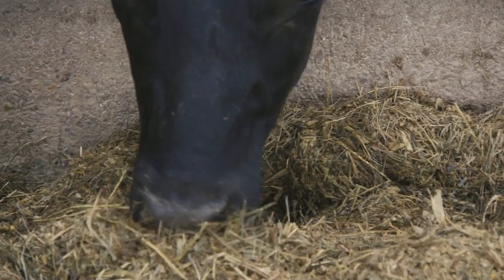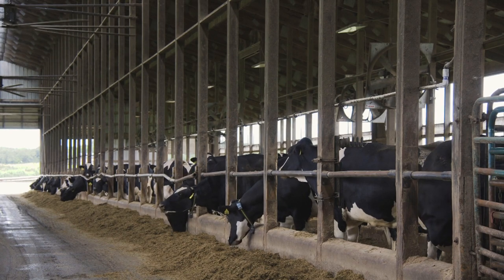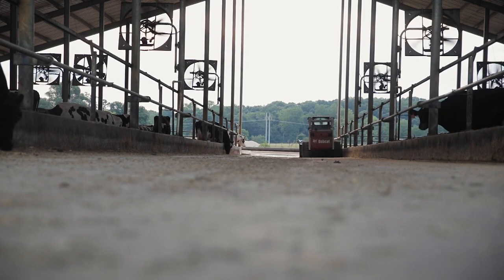So in the summer, we're going to be targeting 200 to 400 feet per minute. For naturally ventilated barns and for cross and tunnel ventilated barns, you can put fans over the free stalls, angled down and spaced about every 20 to 24 feet or every other post, so that you can create that fast-moving air in the resting space.